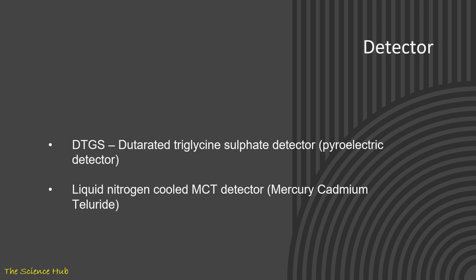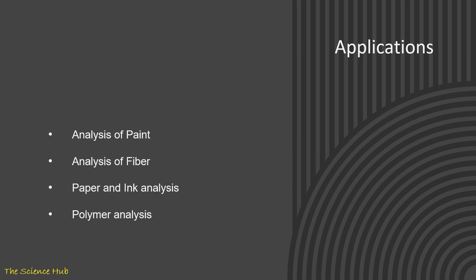There are two types of detector generally used in FTIR: DTGS and MCT type of detector. DTGS means deuterated triglycine sulfate detector, which is a pyroelectric type of detector. Next is liquid nitrogen cooled MCT detector, which is known as mercury cadmium telluride type of detector.